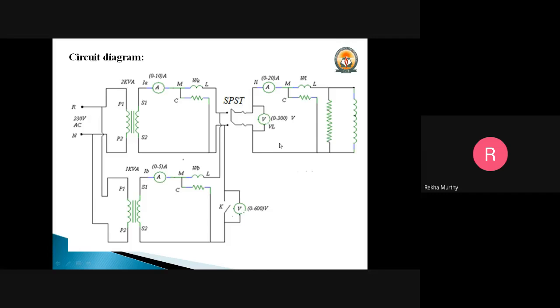So what will be the procedure? The connections will be made as shown in the figure. With the SPST switch open, the supply is switched on. The reading of the voltmeter connected across the switch K is observed. If it reads 0, as we did in the previous session, which means the two secondary EMFs are opposing, then the switch K will be closed. If it reads twice the voltage, we need to interchange the secondary of either of the two transformers.